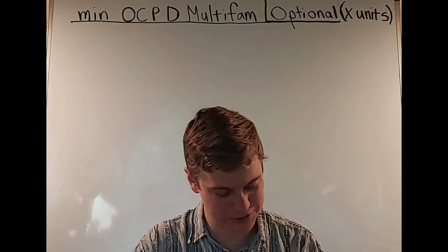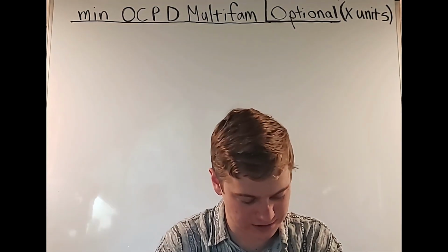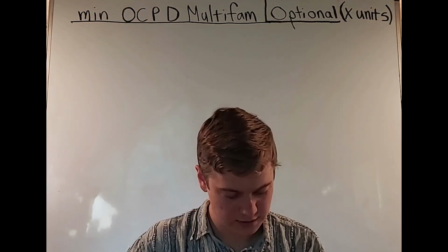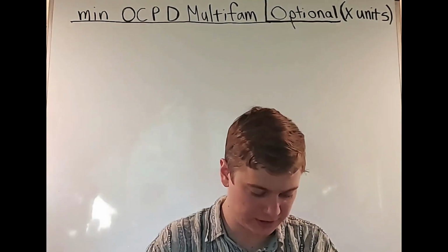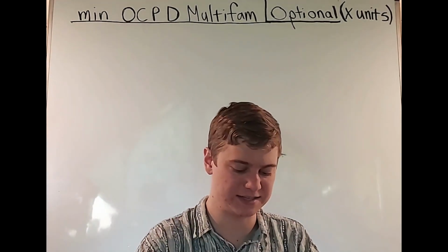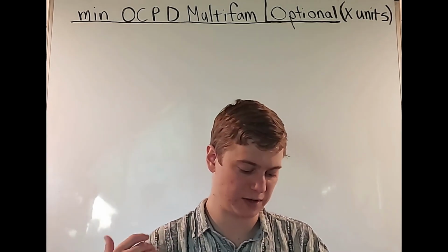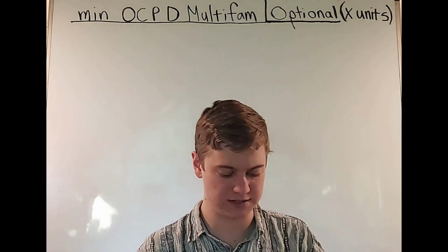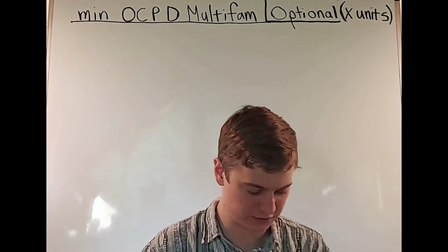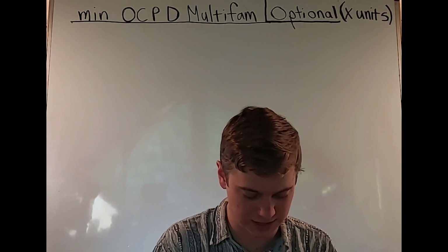Okay, we see table 220.84. We're going to be using this table to figure out our demand factor based on how many units we're working with. We see this is for 3 or more multifamily dwellings, and we see on the left side the number of units in a column going vertically, and on the right we see a similar thing except it's demand factor and it's a percentage. So we look at the number of units we have on the left. For example, 3 to 5 units gives us on the right side a 45% demand factor. Let's go down to something random. 16 to 17 dwelling units is going to give us a 39% demand factor.